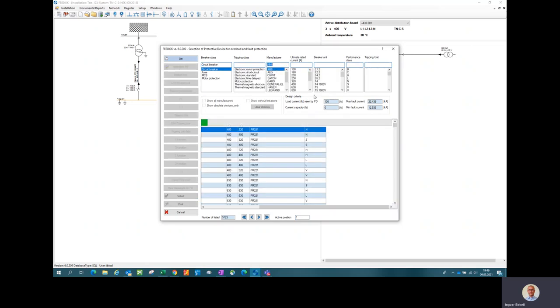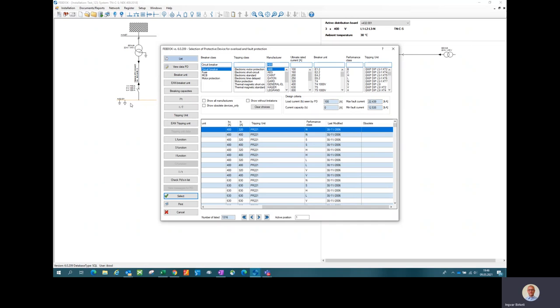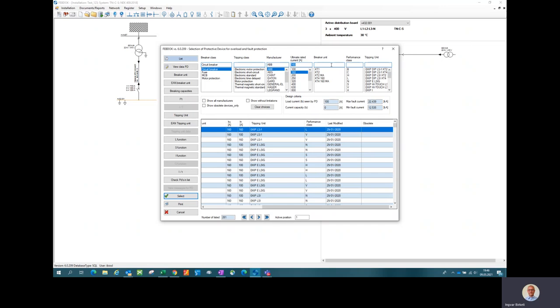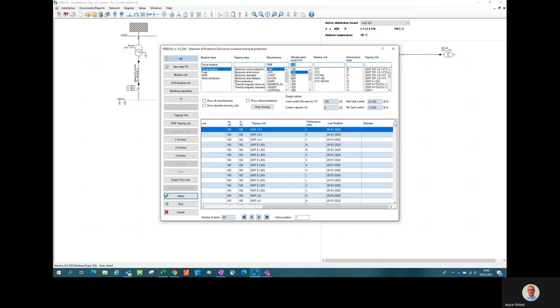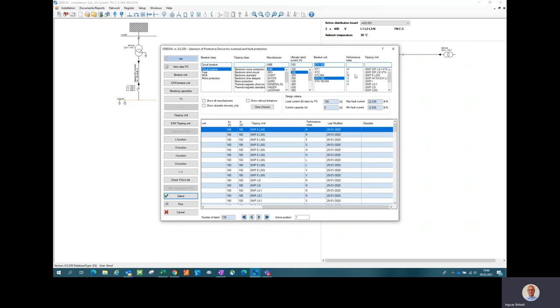Since I used ABB on this first one, I would like to have the same manufacturer for the rest of the protection devices to achieve cascade and selectivity. For most of the manufacturers, you have to use 160 amps to get conditions right for selectivity downstream. There are some exceptions from that. For instance, Schneider has some 100 amps circuit breaker that do the job. Most of them manufacturers you have to go up to 160. I choose this one, normal breaking capacity.